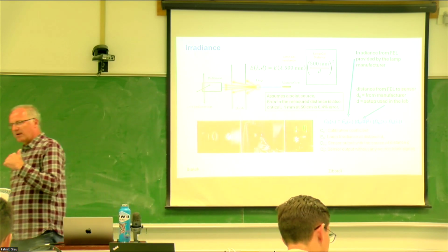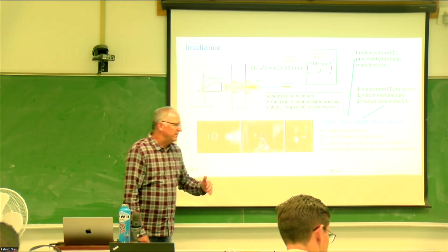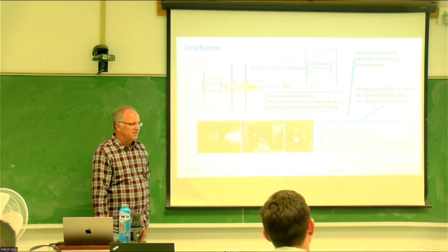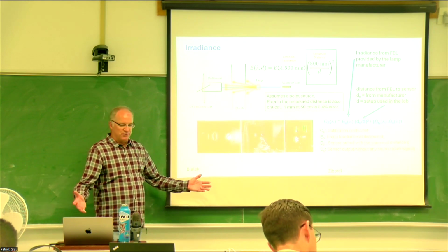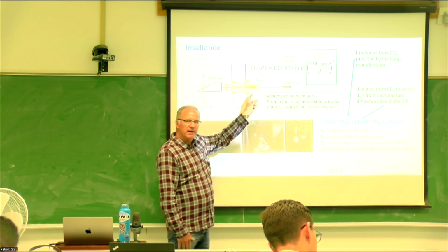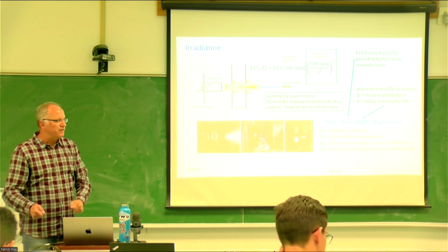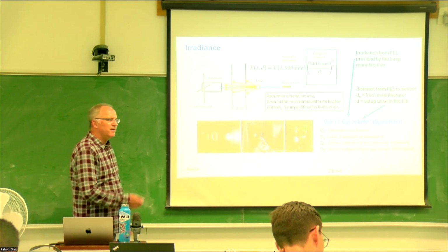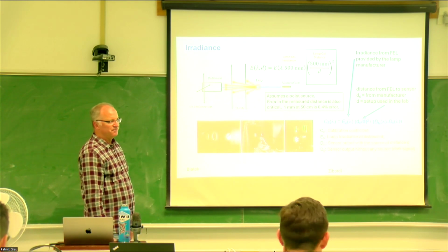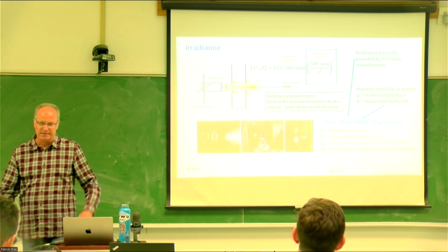To paint this room, it cost me $6,000 just for the material for the paint. So these are the highest absorbing paint you can buy on the planet. Because what we're trying to do is calibrate, the only light source we want in this room is from that lamp. So if you go into my room that I've set up, turn off the lights, shut the door, you cannot literally see your hand, even at a short distance. It is totally dark, zero photons.